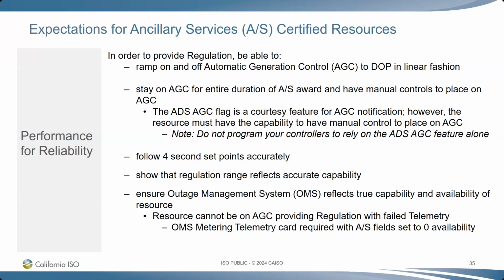Resources cannot be on AGC providing regulation with failed telemetry, so it's important to have the telemetry settings correct. If there are problems with the telemetry, the OMS metering telemetry card is required with AS fields set to 0 availability.